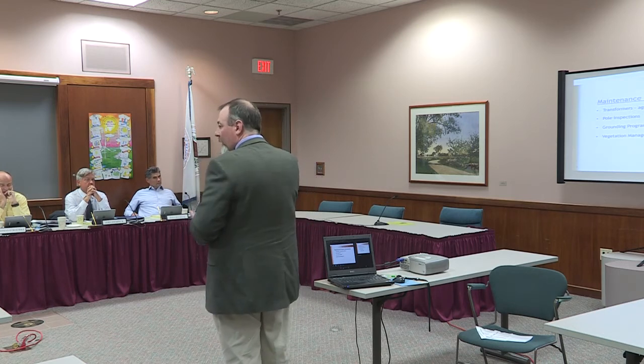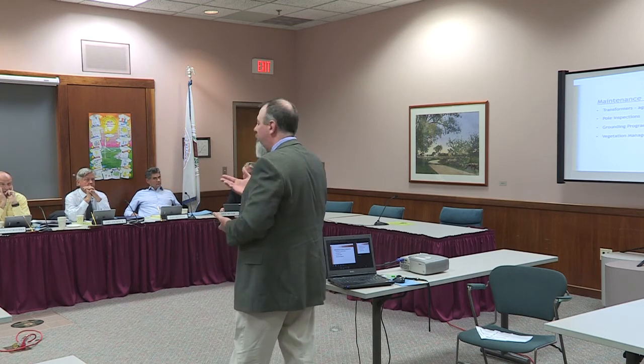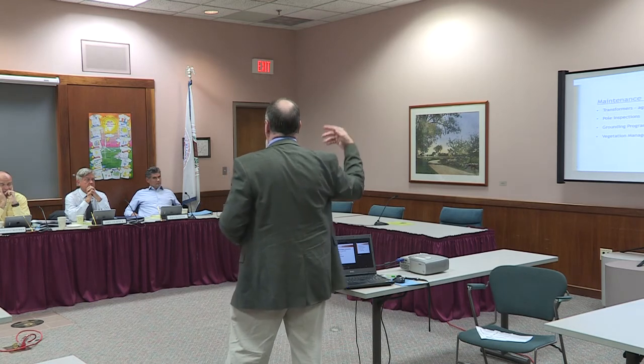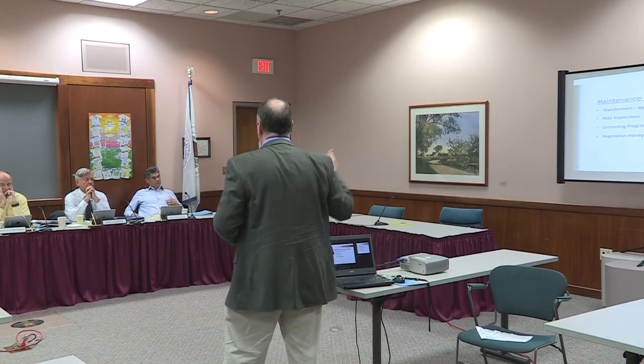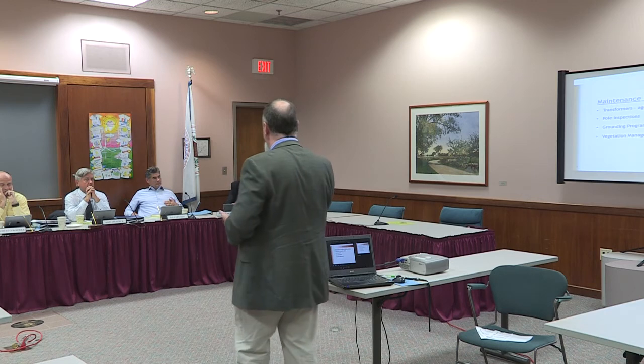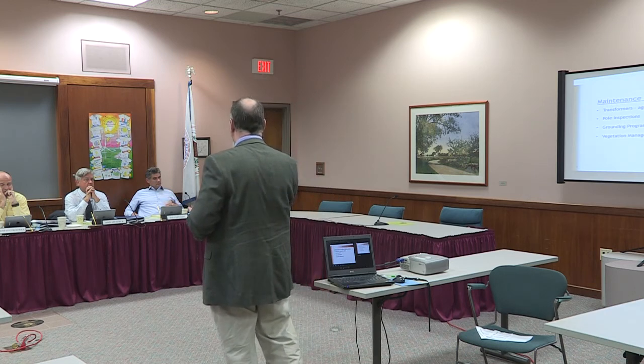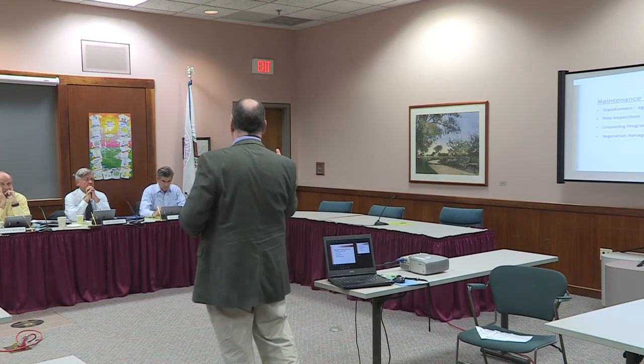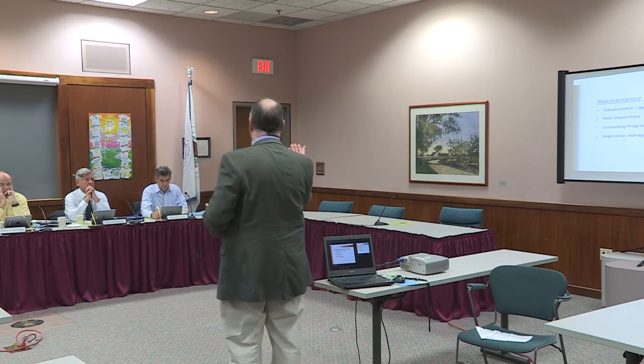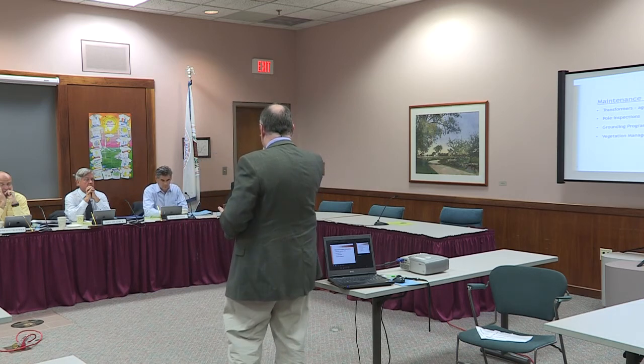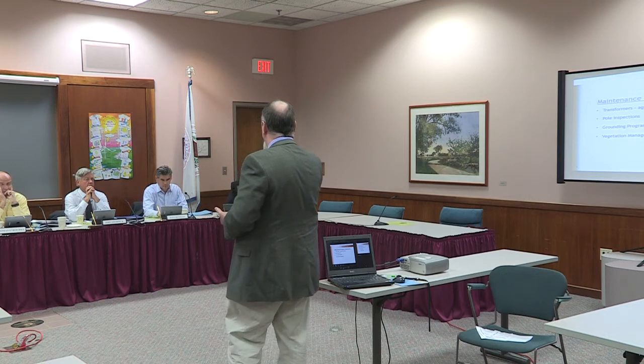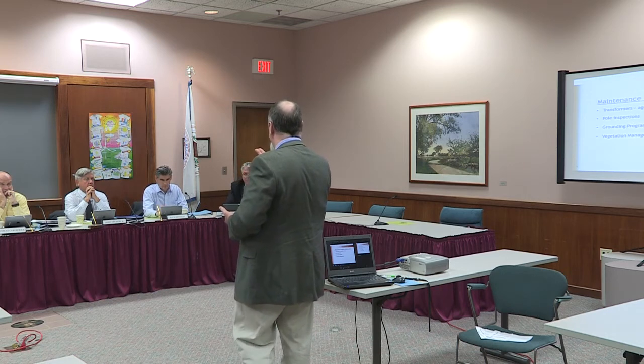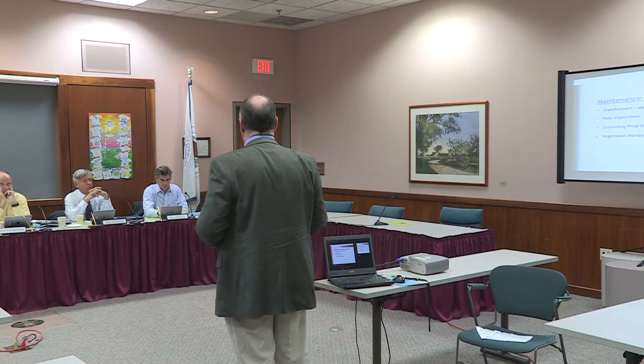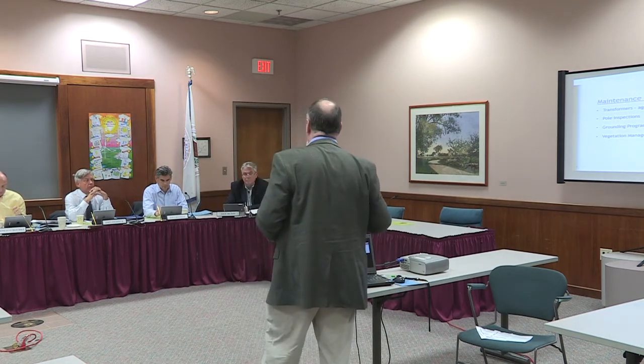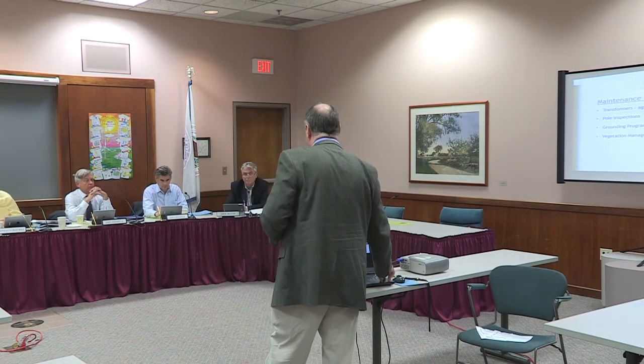And on the O&M program to replace transformers, those are the types of things you'll be attacking first. It's not just age, but you also have to factor in loading and condition, kind of a triple play. It may be old, but there may be a transformer that's a lot younger where you start seeing stains from oil leaks developing. So there's your two factors, age and condition. All these O&M programs are important to maintain system integrity and safety.